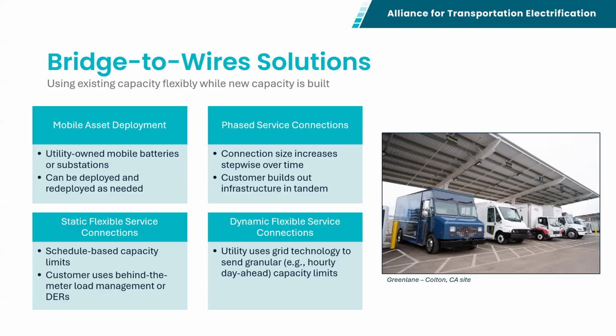With a static flexible service connection, the capacity limits for that site are schedule based. So you might get 4 megawatts overnight all the time, 3.5 megawatts throughout the day most of the year, but in the most constrained times of the year, only 2 megawatts. If the customer can operate within those limits—whether by behind the meter load management, behind the meter generation, or changing operating schedules—they can get their full 4 megawatts for some hours of the year.